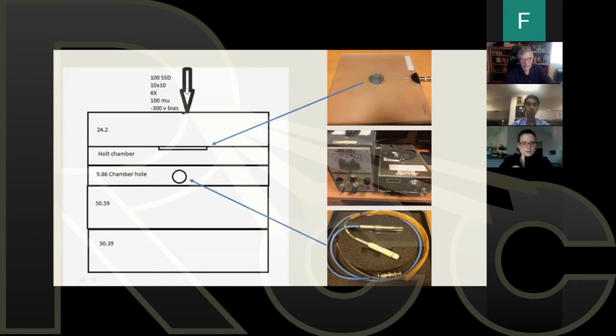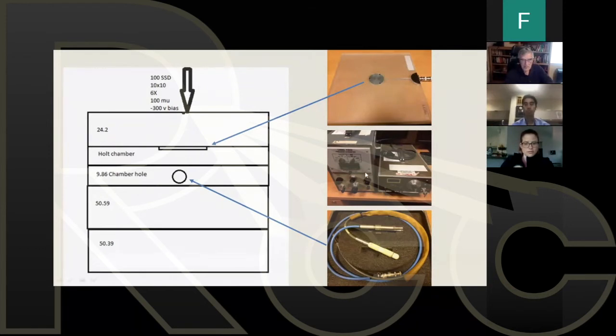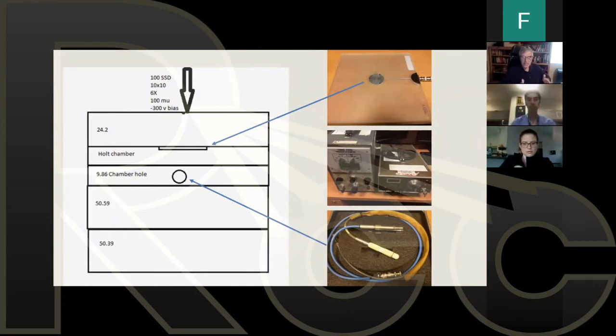I set 100 SSD with a 10 by 10 field, and I use 6 MV X-ray, 100 MU, with negative 300 volt bias. And I irradiate the whole block, and I will have the Holt chamber here, the parallel plate chamber here, and I will substitute my different chambers in this hole for different readings. I will also substitute my electrometers to compare their readings. So this is my setup for intercomparison. And I do this at least once a year.